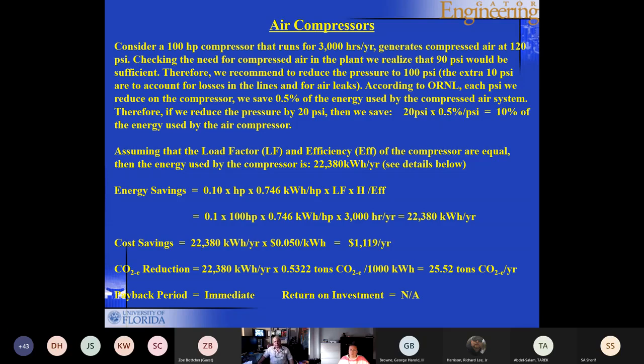Now, if you assume that the load factor here, we're going to make a simplification. We're going to assume that the load factor and the efficiency have the same value, like let's say 80% for each, only so that they can cancel. And you don't really have to make that assumption. You can plug them in, and your equation will be just fine. If you look at the equation down below that statement, you will see that it has the load factor and it has the efficiency, the LF and the EFF. So if you cancel LF and EFF, you get to the next line, which is the 0.1, which is the savings that you had, the 10%.